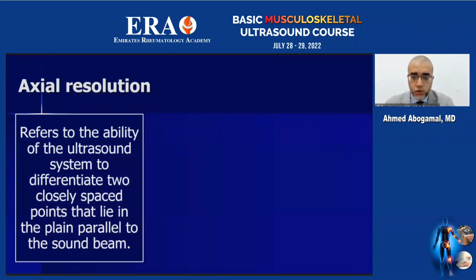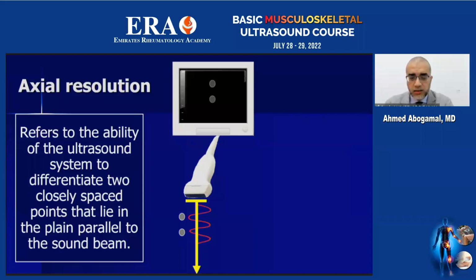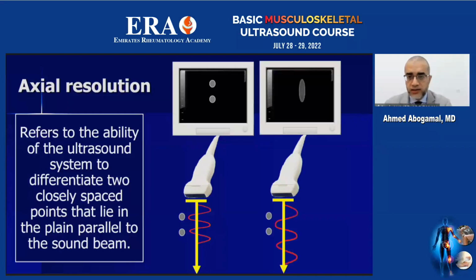Axial resolution refers to the ability of the ultrasound system to differentiate two closely spaced points that usually lie parallel to the ultrasound beam. As you can see here, these two points are received by the ultrasound machine as two different points, which means we have a good resolution. Usually, if the distance between the two points is related to the wavelength, or usually less than the wavelength, that means we have a good axial resolution. In the other scenario, if these two points are received as one point, at that time we have a bad or low axial resolution of the ultrasound machine. And in turn, this can miss some pathological or physiological lesions inside the joint examined.